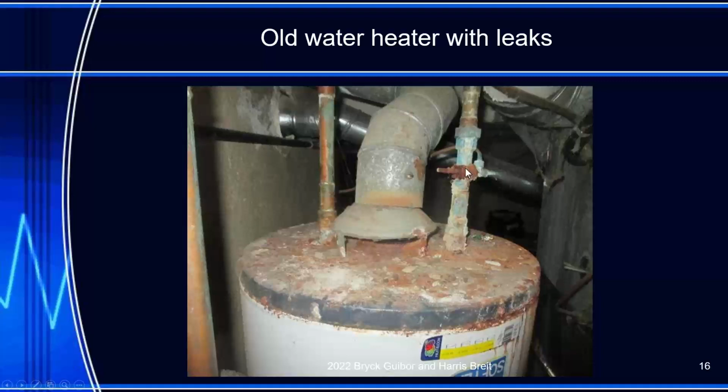So if we take a look here, I'm getting electrolysis and leakage. Here you can see the pipe is starting to look like it's burned bad and lots of rust around the perimeter. In the back is my furnace. Here's my flue pipe coming up, and it's punched a hole either through the side and it's going up or through a chimney or something. But this thing back vented so long, it created oxidation up the copper pipe right here. See it?